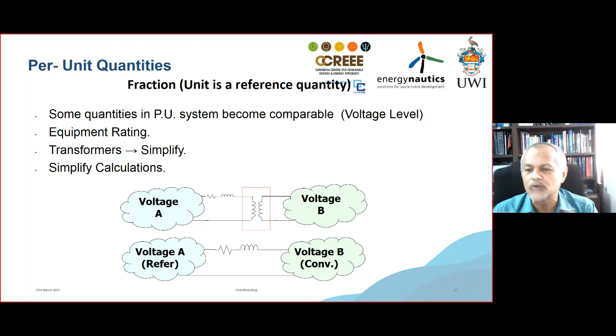The per unit system removes a lot of the problems, for example with transformers. I can remove the transformer network from a per unit system by just replacing the transformer with an equivalent impedance. With that, I've converted this power system into an equivalent—and I'll use the word here—DC type of system. I'm only using DC to mean that I can now start an analysis equivalent to, not equal to, but equivalent to how you would do a DC calculation. It simplifies your calculation throughout the power system.